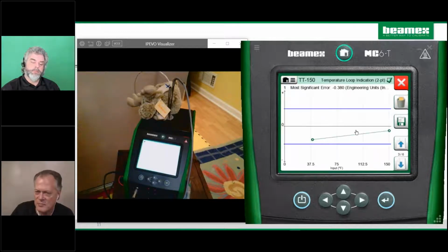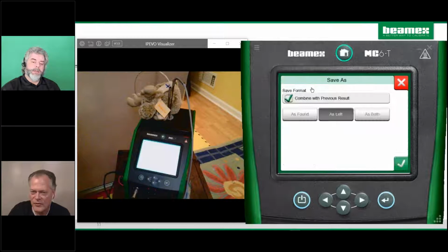So this one is off. When I was working with my food customer, we saw this kind of phenomenon, and I asked, what's going on? These numbers should be together. And he said, well, the DCS input card needs to be adjusted. So really to fix this, we need to do both. We need to do the RTD transmitter as a combo and then verify that the 4 to 20 is working right. But I'll save this one also as an as found.